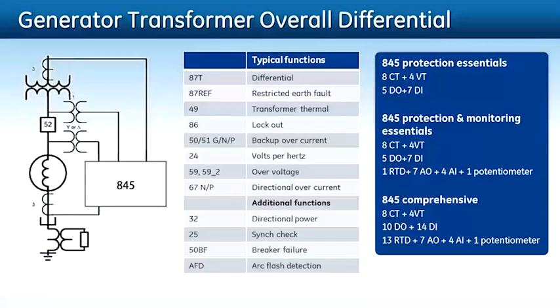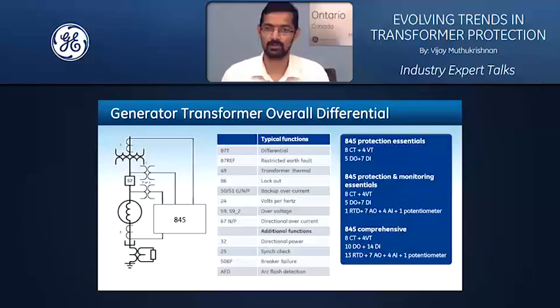The next case is where you consider the generator and the step-up transformer as a single zone, and you provide an overall differential. Here you are essentially applying a transformer differential protection for the zone of a combined generator and transformer. So you will treat this as a two-winding application when you have a generator connected to a two-winding transformer. You can have an overall differential relay that is equivalent of a three-winding application if you have a common step-up transformer for two generators. That is also possible. Apart from the application need change, the type of protection you apply remains similar to two-winding and three-winding applications. In the case of a combined zone, you will apply the phase and magnitude compensation for one end. The other end will not have any phase and magnitude compensation, so to say, because you treat it as a baseline. And the monitoring and diagnostic functionalities are applicable across the same applications.